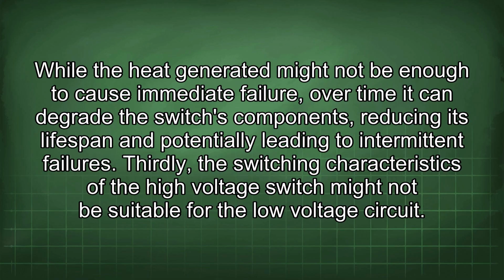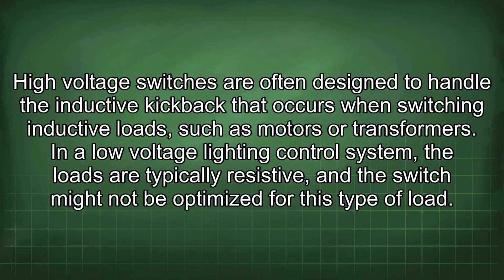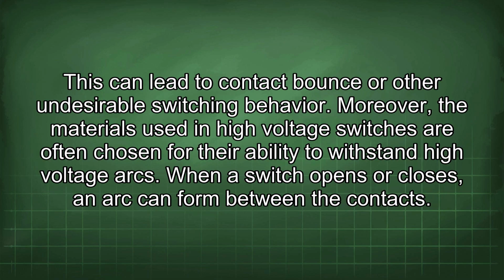Thirdly, the switching characteristics of the high voltage switch might not be suitable for the low voltage circuit. High voltage switches are often designed to handle the inductive kickback that occurs when switching inductive loads such as motors or transformers. In a low voltage lighting control system, the loads are typically resistive, and the switch might not be optimized for this type of load. This can lead to contact bounce or other undesirable switching behavior.